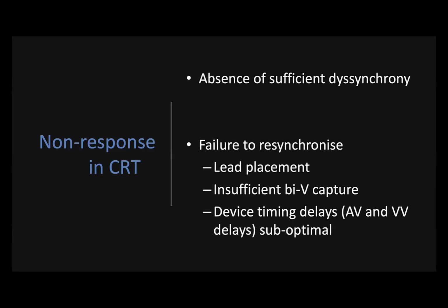And then finally, and just as importantly, the timing of filling, the diastolic performance, which I discussed earlier, can be suboptimal. And devices are set up to allow you to change the atrioventricular delay and also the delay between when the left ventricle and the right ventricle contracts. This is extremely important. And I think Hani talked about him and Mirvat occasionally using echo to optimize the device.